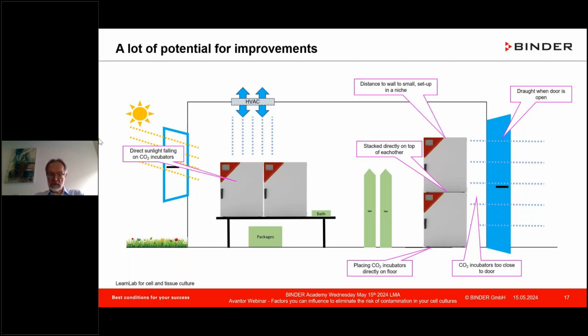Distance from the wall, very important, so air circulates and you don't have any molds developing behind it. Usually that's about 50 millimeters. You should keep the CO2 incubators, tabletop or stack, away from the rear wall. The distance between them is also specified, specifically if you have 180 degrees C or temperatures like that. If you conduct that sterilization and they're close to each other, you will have a temperature influence in the incubating one, which definitely you don't want. You don't want to cook your cell lines. That's what I'm trying to tell you.